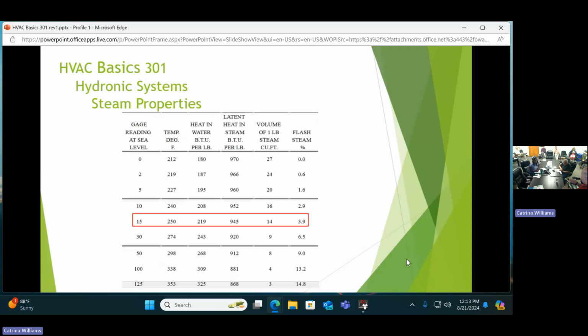So that's an orifice. So you actually put a slight pressure to it. So 15 psi steam is 250 degrees. That's a very common steam pressure that we use in commercial and industrial buildings. Sometimes it'll go higher than that, but we start at 212. 15 psi is the beginning point of medium pressure steam. We see steam pressures all the time in between here, but that's a common one to look at. So I kind of wanted to make a point, and I'll use this throughout the presentation, that 15 psi steam is 250 degrees, which is quite hot.